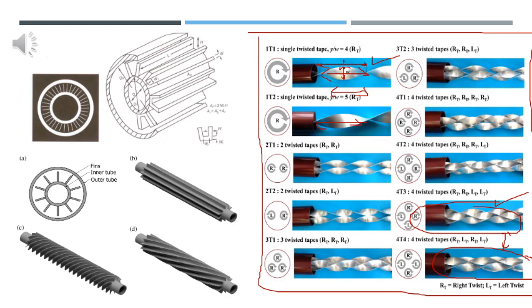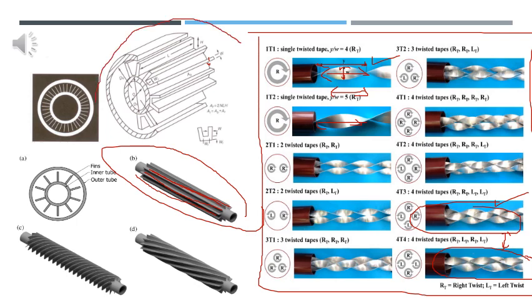The inner pipe may also have longitudinal fins. Longitudinal fins are used particularly for gas service, because gases have a low heat transfer coefficient and require larger surface area and turbulence. These fins are also used in shell and tube heat exchangers for the same reason — to increase surface area. The width, length, and surface area of longitudinal fins can be calculated using formulas from textbooks, though the calculations are more complex.